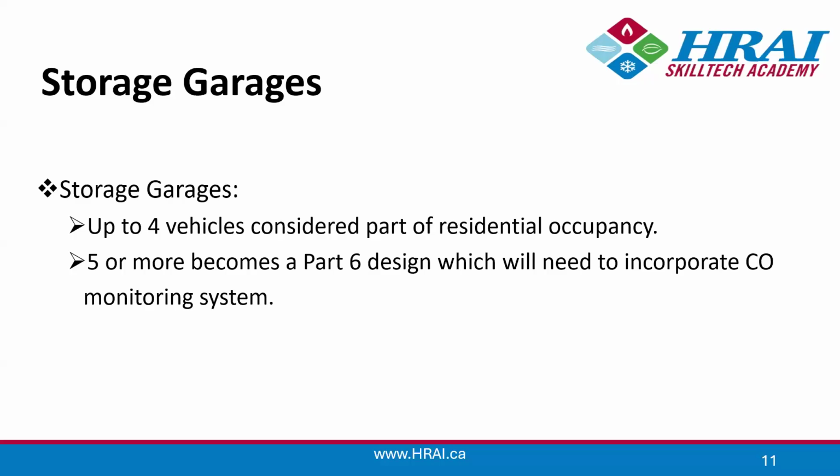So if there are 5 or more parking spaces in the garage or 5 or more vehicles being stored, then this becomes a Part 6 design, which means you will need to incorporate carbon monoxide monitoring or nitric oxide, nitrous oxide. I'll have to find the proper wording for that.